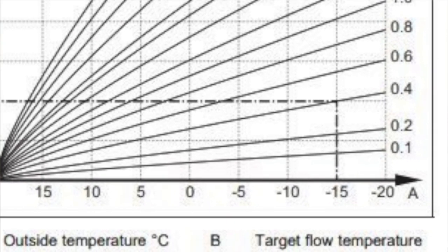This means that at 5 degrees outside, we have the radiators running at about 43 degrees. At 0 degrees outside, it will be about 46 degrees in the radiators. If we were able to be comfortable at a lower temperature — a lower curve — then we'd improve the efficiency of the heat pump. But we know there are parts of the house that would benefit from better insulation and reduced drafts, so we need that level of heat at 0.9 to be comfortable. If we manage to do some more insulating this summer — maybe the downstairs floor or some wall insulation on that external wall — then we may be able to reduce the heat curve slightly for next winter.